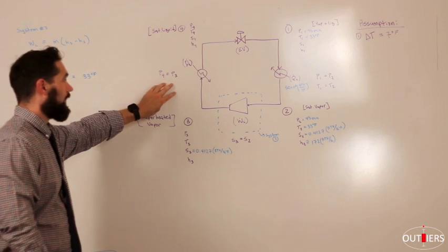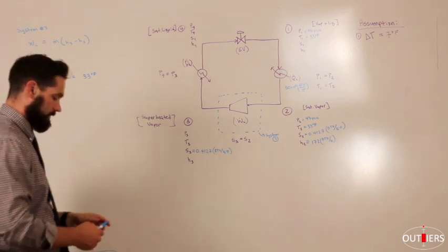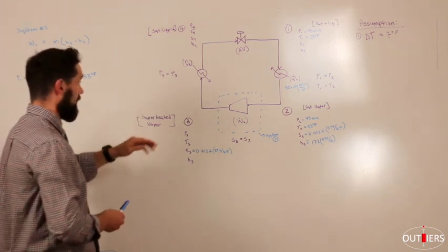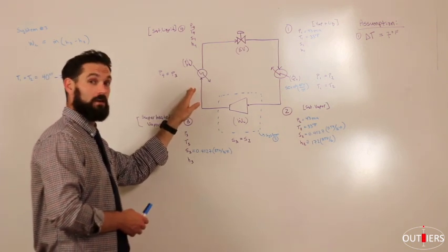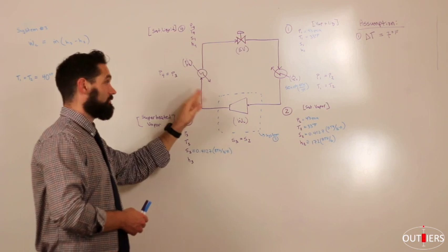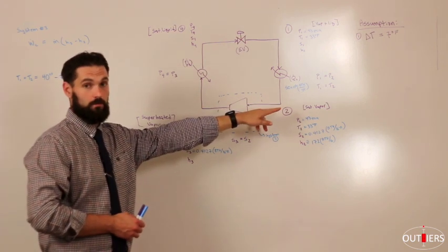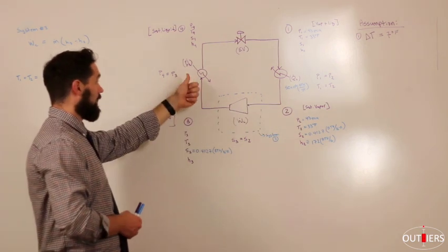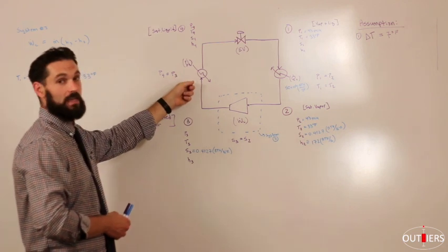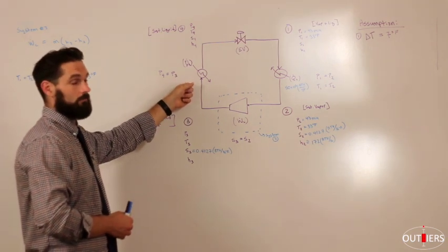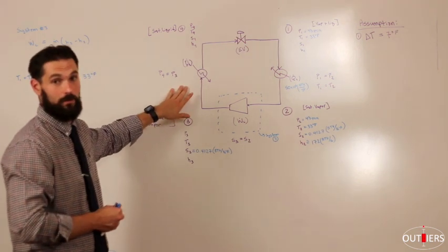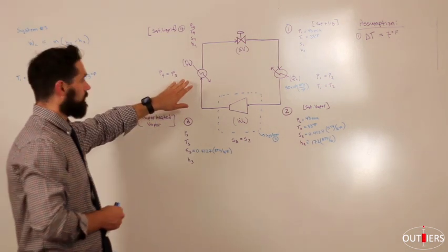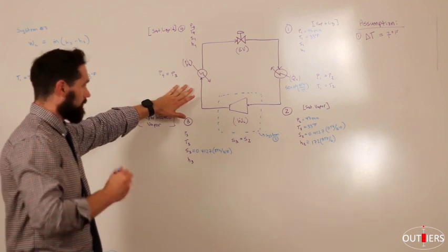When the ambient air is the hottest, this refrigeration system is going to be under the most stress. If you size it for a cooler temperature, you're not going to achieve your needed BTUs over here, because it can't dispel enough heat on this side. Once you get into exchanger design, you probably didn't give it enough surface area. But for right now, just know that you want to size this for worst case scenario.